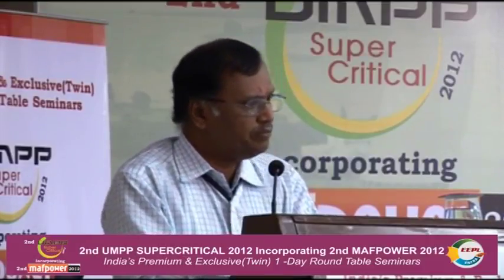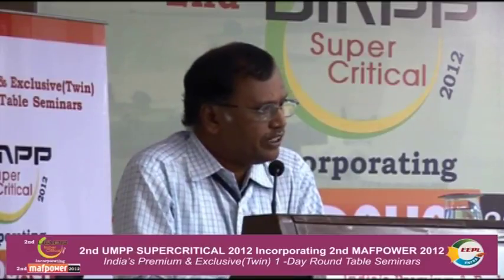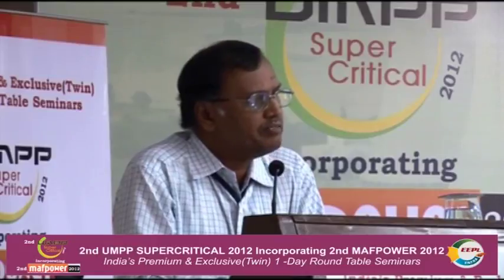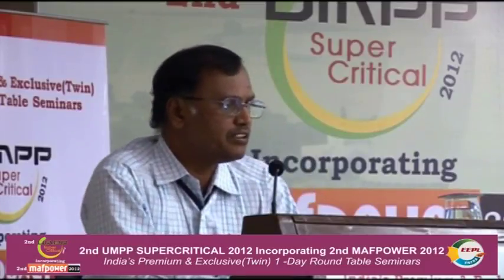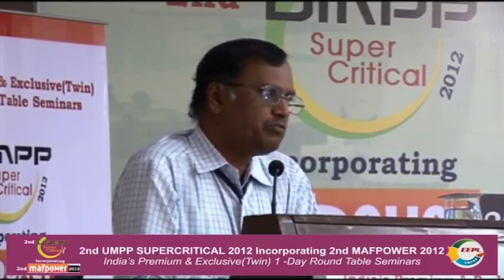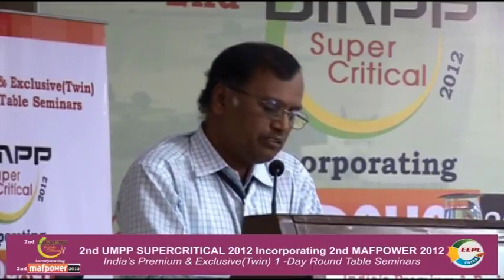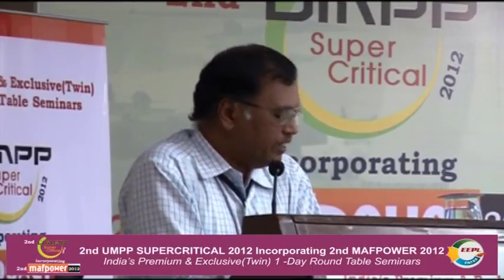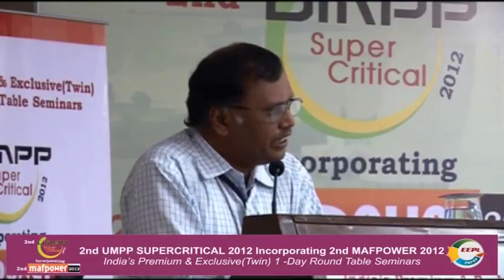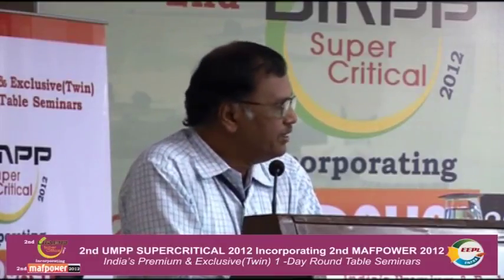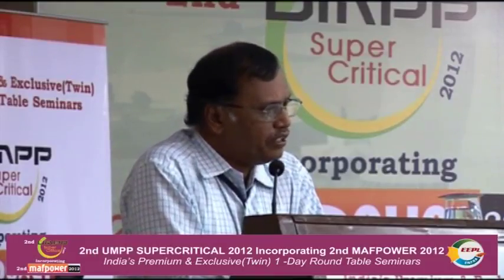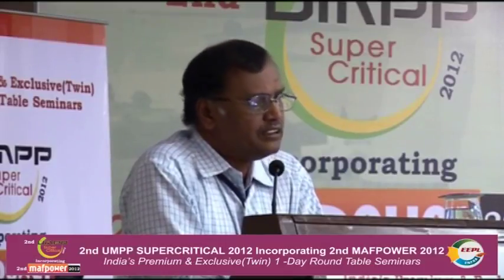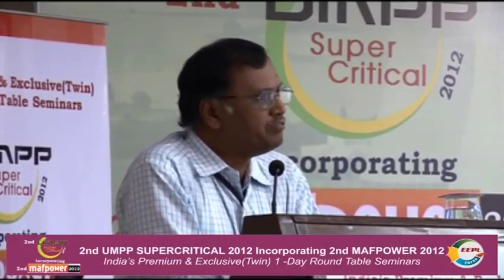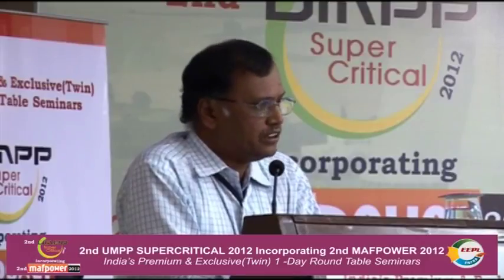the concept is that the mass flow through all the heat transfer circuits from economizer to superheater is the same, whether at full load or low load. At very low loads, below 40%, it is not possible to maintain the once-through flow. Therefore, we are going for a small recirculation system. That's the concept. And the salient features of this boiler are these. This boiler is suitable for variable pressure operation. Up to 1000 megawatt, we can go for single reheat. Double reheat is not economical.